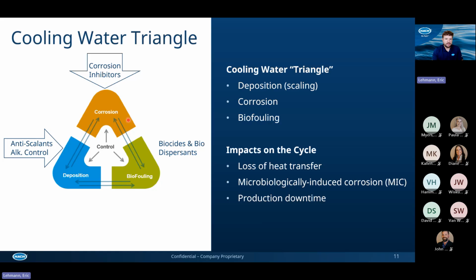From there up top, we have corrosion. So corrosion is really caused by many factors. It can be caused by maybe low pH, maybe an acidic environment. So where they're maybe trying to mitigate the scale, maybe they're adding acid to bring the pH down a little bit. Too much acid could actually cause corrosion. Chlorides are another thing that can really cause corrosion on stainless type material, causing pitting, small deep holes in the metal. So they're really trying to mitigate that. Sometimes they have to feed corrosion inhibitors, so maybe a phosphate type corrosion inhibitor to really protect that metal from any type of corrosion. And then lastly, the biofouling.